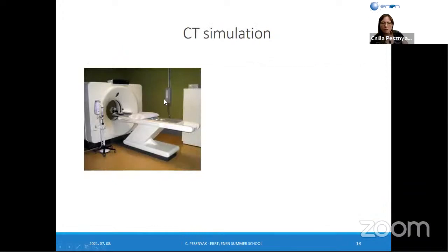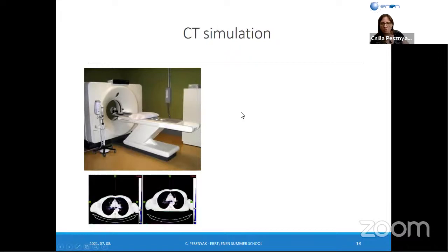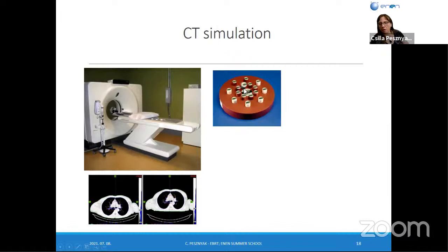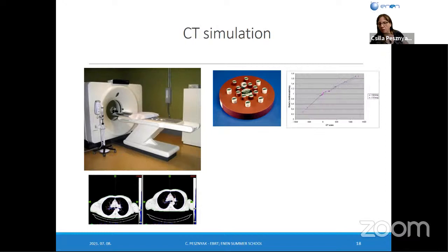Here you can see one CT simulator. It is equipped with a special laser system. We also use a flat table, not a spoon-shaped table, because otherwise the anatomical structure would be in another place, and because the accelerator table is flat, we also have to use a flat table for the CT. We also use a special phantom for the calibration of the CT. For the treatment planning system we need Hounsfield numbers and relative electron density, and for every CT we need to make a special calibration curve and upload it into the treatment planning system.